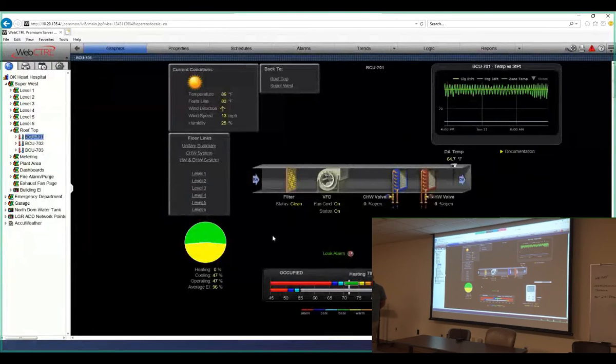Gotcha. Because we used to kill the fan, and that was the old theory, okay, we kill the fan and the valve. But just the fan running helps with the evaporation. So if you're already overflowing and there's a danger of flooding something with water, why not just let the fan evaporate a little bit of the water, so that it may help reduce some of the water that's inside the unit.